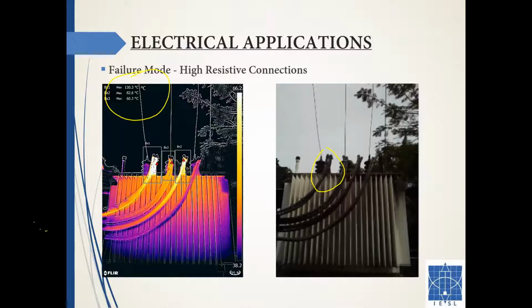You get it to the maximum load. The National Fire Protection Agency 70B standard says your installations should at least be 40% loaded. But we say it should be 100% loaded, so you get the maximum anomaly possible and you know what's the worst. From there you can work.